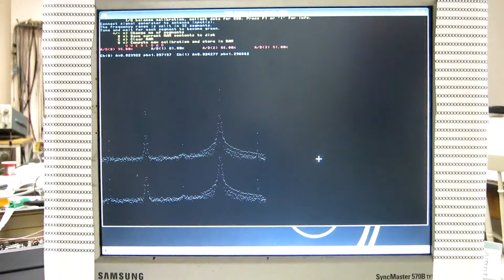So I leave it running like this to stabilize before going to the mirror image balancing. To go to the calibration menu, that's X and C, and first calibrate the IQ phase and amplitude, that's A. And we have to reduce the level a little bit, like that. And then I have to sweep the frequency in steps of 3 kHz, that's 96 divided by 32.